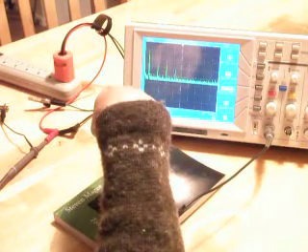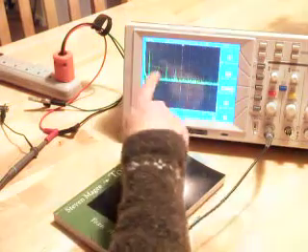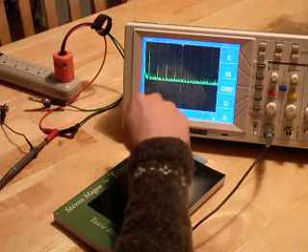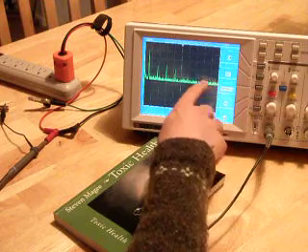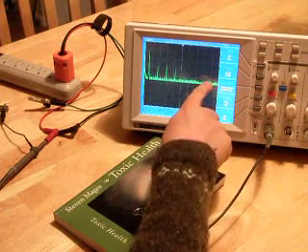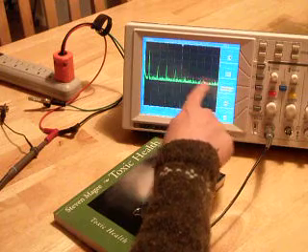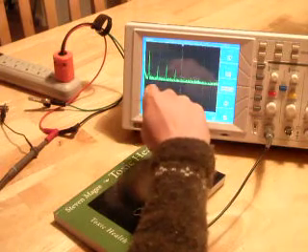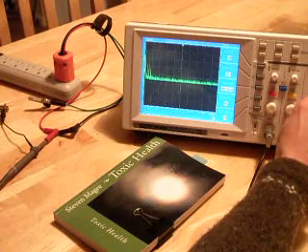And that's the way the system should look when you're analyzing it — there shouldn't really be too many harmonics. These harmonics here are a little bit concerning, but the rest of the system seems to be okay. One of the problems we do have, though, is this constant fluctuating of frequencies of electrical noise. And if that gets too bad, you may actually start getting radio waves coming out of your wiring. As you can see, it does actually flicker quite a bit.